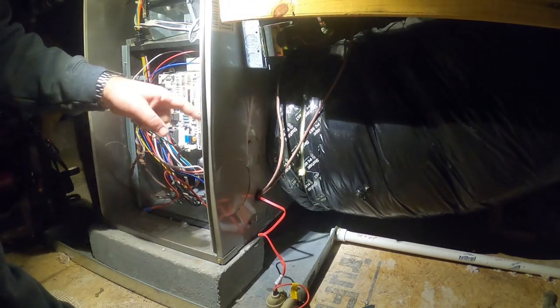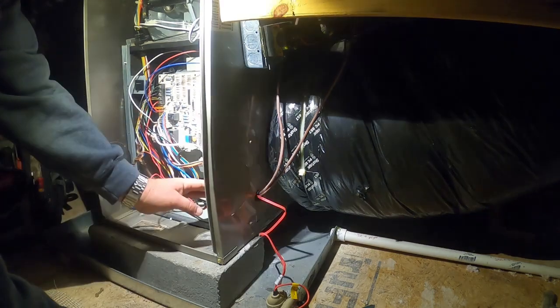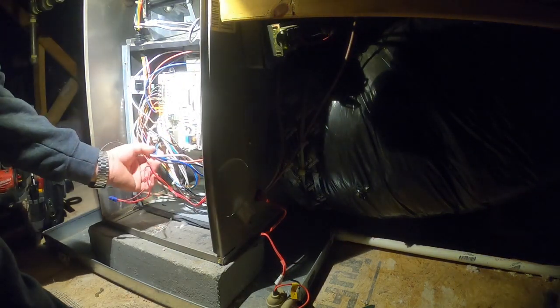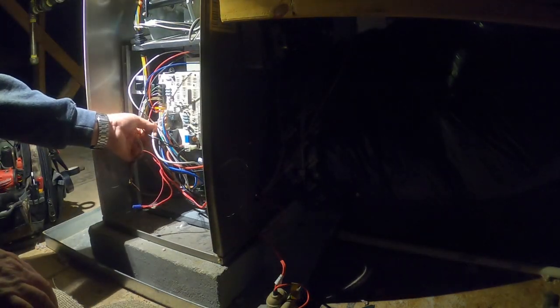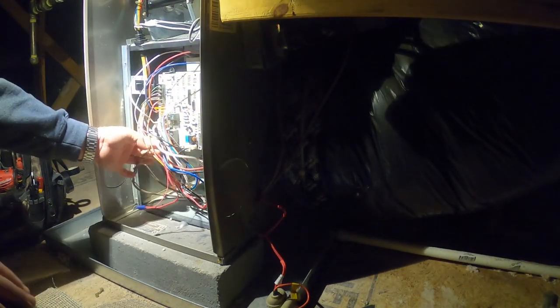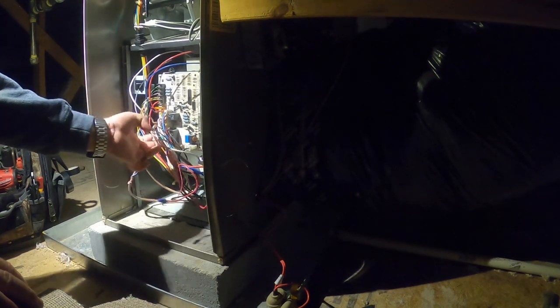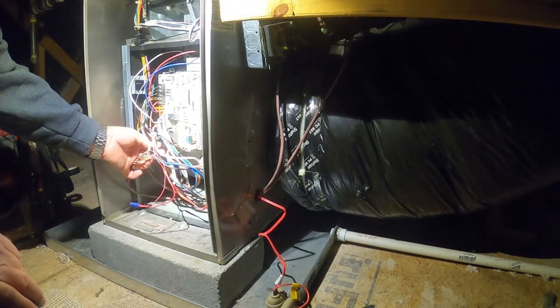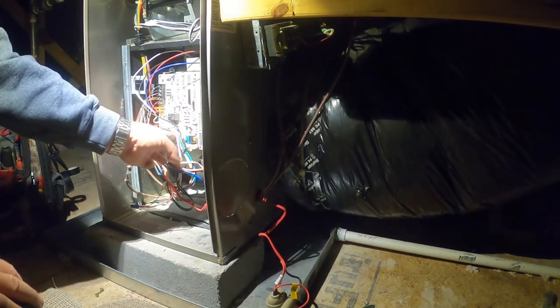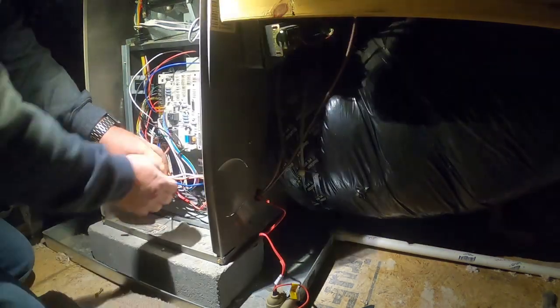Looks like it's going to be a universal motor in there. I don't know if that's part of anything they were in there trying to do. There's our blower neutral, there's our two. We're running a heating speed and a cooling speed, I can see right there. And there's going to be our unused.